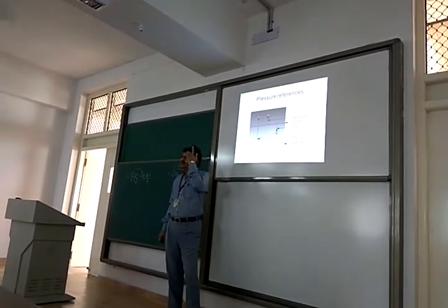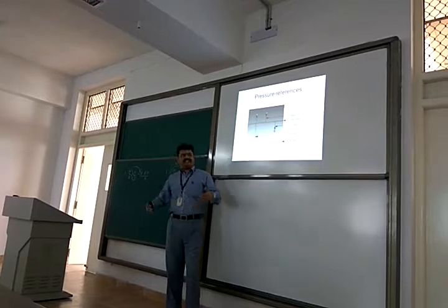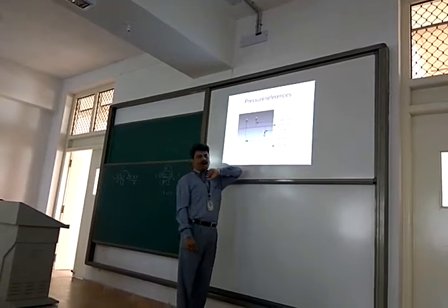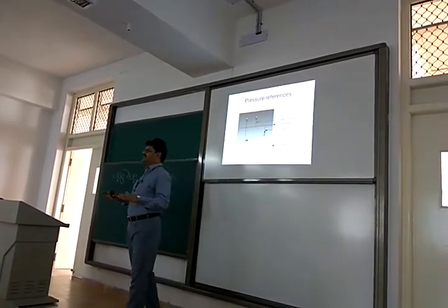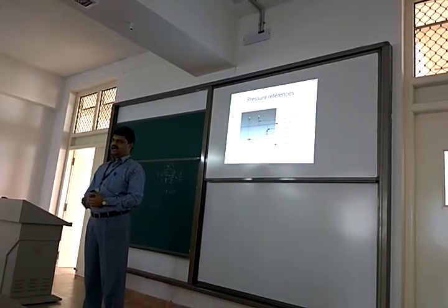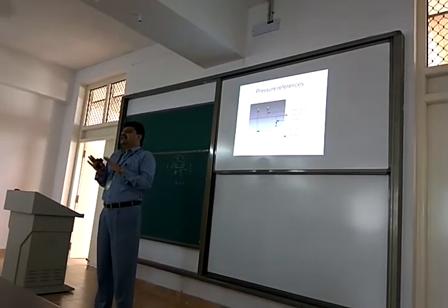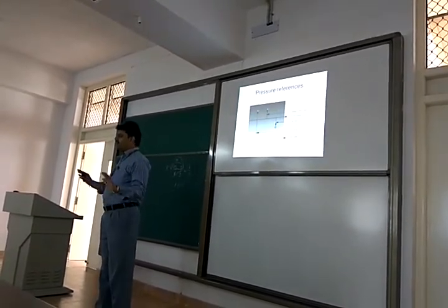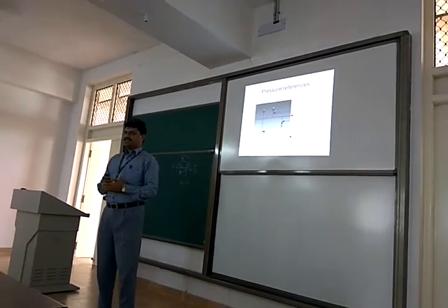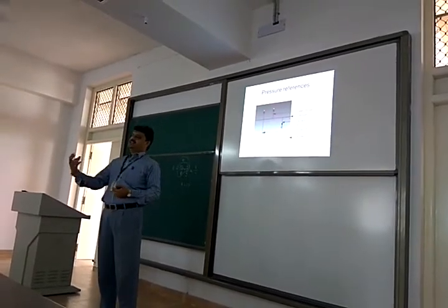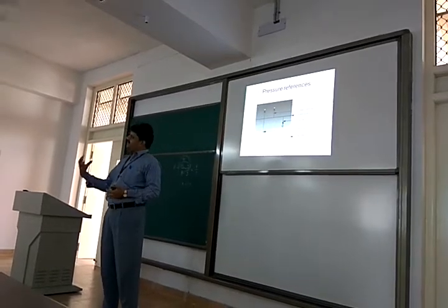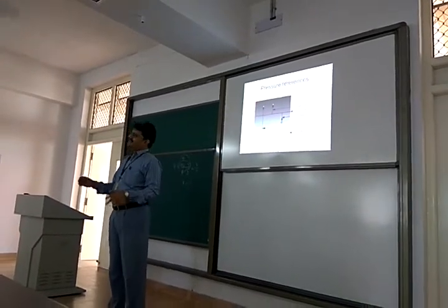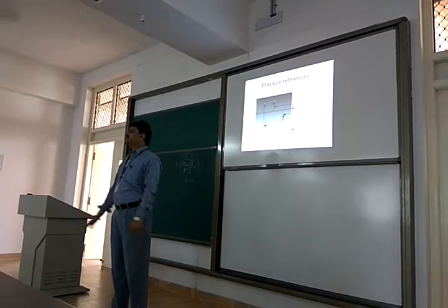This is very difficult to achieve many times. Because of that, we created another reference, that is atmospheric pressure. Here it is. For all practical purposes, we will be using atmospheric pressure as a reference for measurement. So we take atmospheric pressure and call that our zero pressure. It is not actually zero, it's not absolute zero, but for all our practical purposes, we will say zero pressure. For gauging purposes, that's why it is called gauge pressure. For measuring purposes, we made that zero. But actually, it is 1 bar pressure from absolute zero. Hereafter we reset that to zero, so it's called gauge pressure.